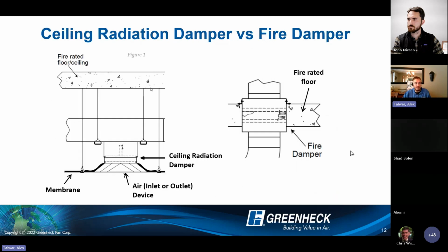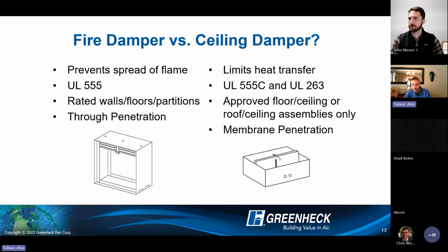Here's a good side-by-side. On the left, a ceiling damper protecting that ceiling membrane; on the right, a fire damper protecting that full penetration of, in this case, a concrete floor. Horizontal fire dampers are pretty limited in how they can be installed themselves. So that's a good side-by-side difference between the CRD ceiling radiation damper and the FD or DFD fire damper. And I do also have a slide that spells it out too. So there we go. You can see they're tested to different standards as well, right?